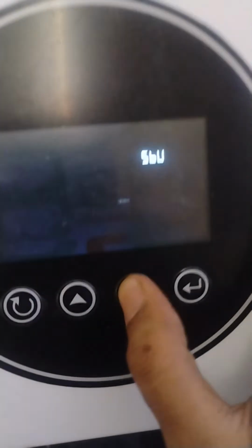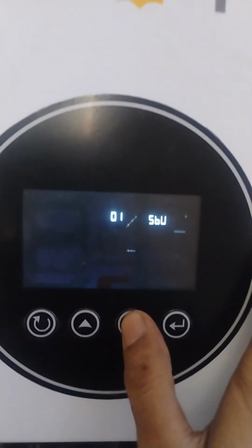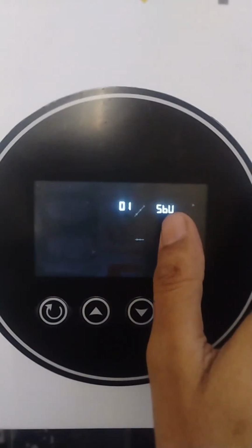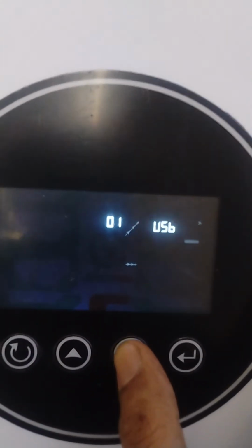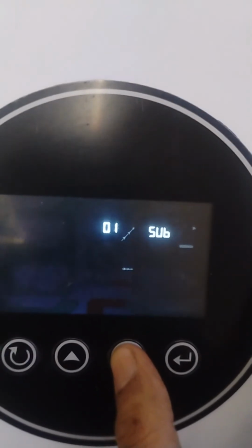SBU - the default mode you will get is SUB, that means solar, utility, and then battery. But I have made changes to my preference. You can change it like this: solar only, or utility-solar-battery, or solar-utility-battery, and this is my setting: solar, then battery, then utility. So solar will be in first priority, afterwards it drains the battery, and after the battery drains lower than the set voltage, then it will switch to utility mode.